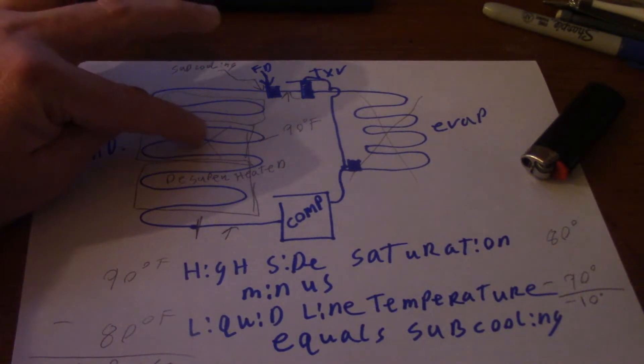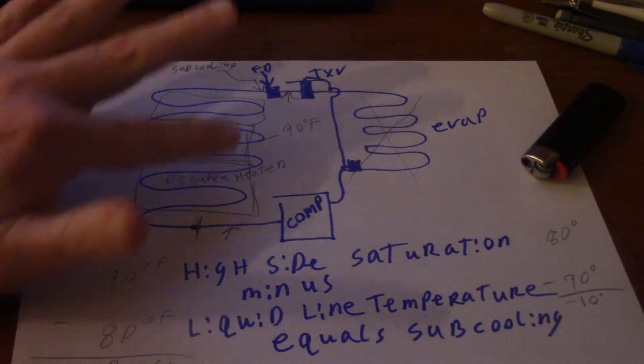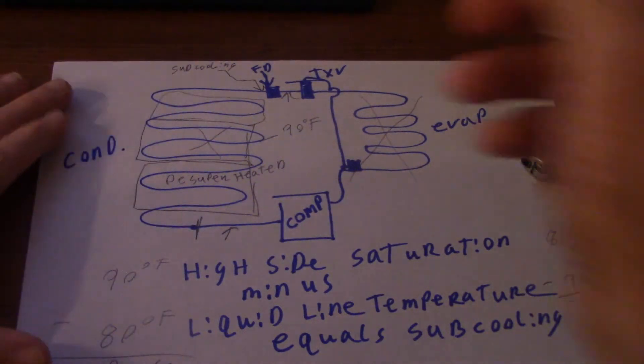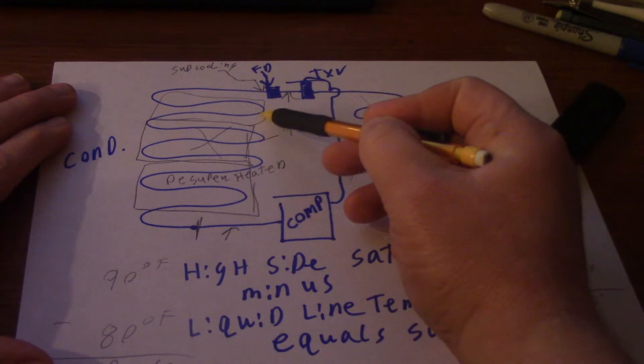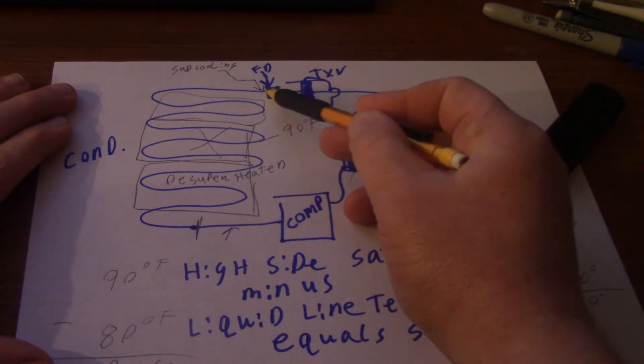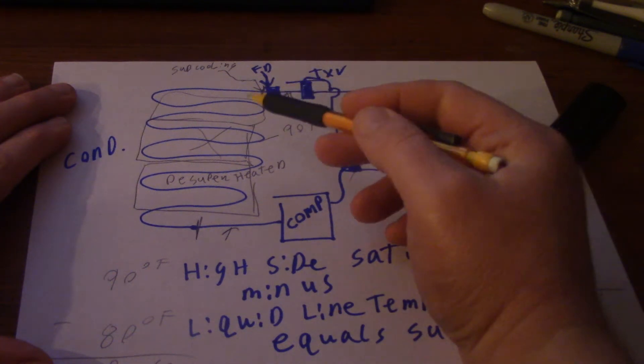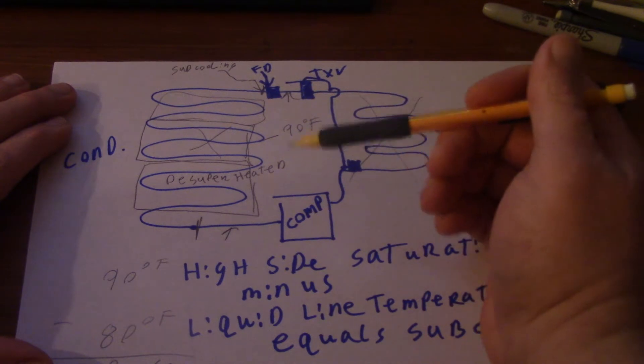Anyways, that's the temperature, the change of state is going on. We're not adding heat, we're not removing heat, we're just changing state at 90 degrees. Once we go through that last portion of the condenser and get right there on the outlet, that's where we can have subcooled liquid, high pressure, warm subcooled liquid for system operation.